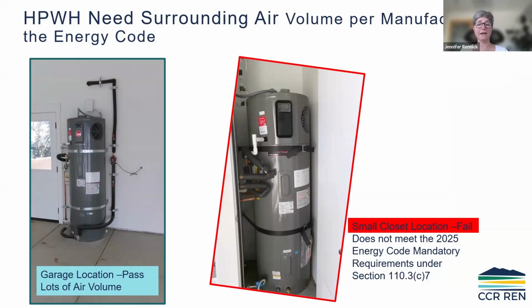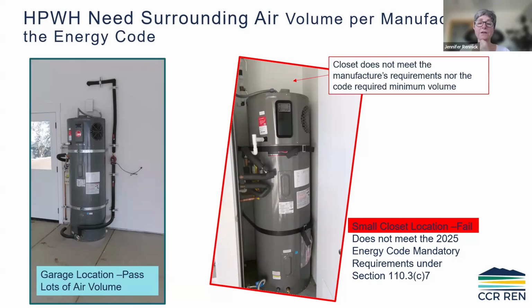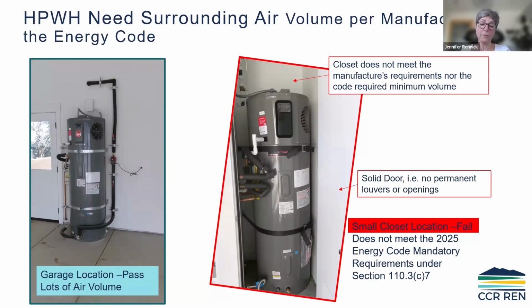The other thing we're seeing, though, is not designing a closet or a space large enough. This gives you an example: a garage location passes lots of air, the pipes are insulated. That's a good install there on the left. And on the right, this is from a job one of our HERS raters was at. There was an alcove designed and a closet designed just off of the garage, but the closet itself didn't meet the minimum code requirements for the volume needed. And then the door was solid, no permanent louvers or opening.